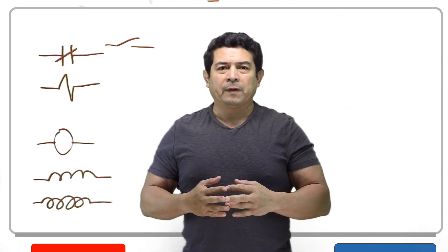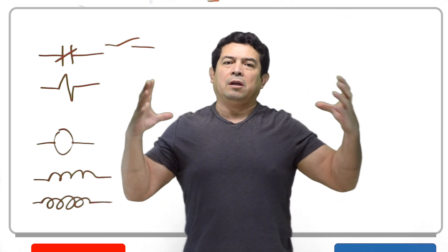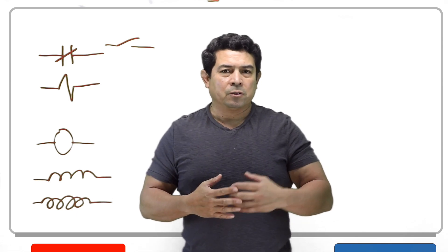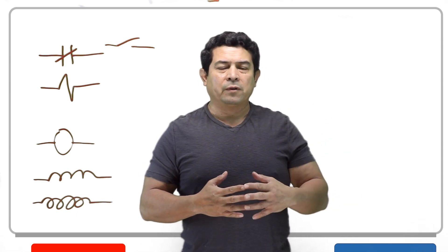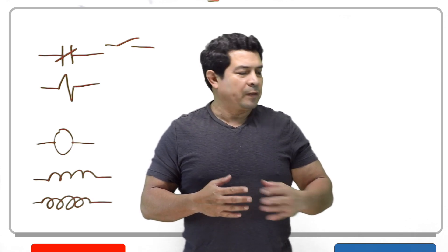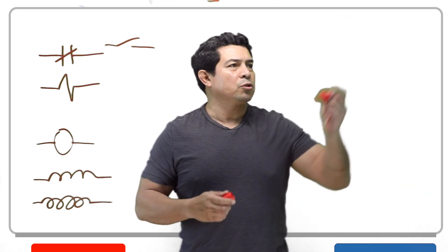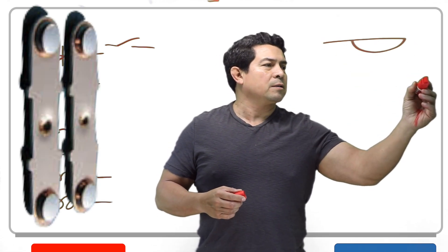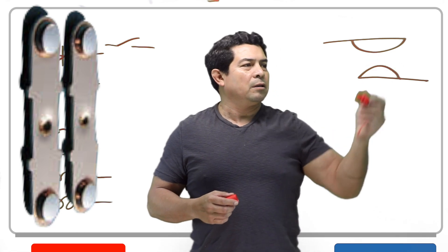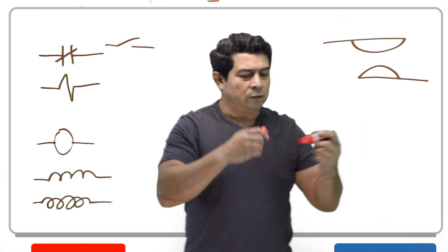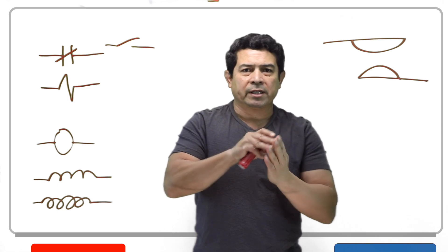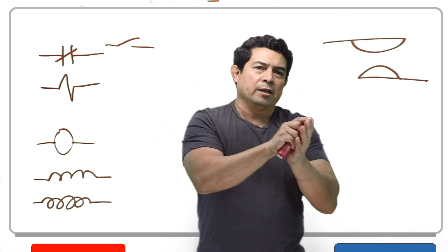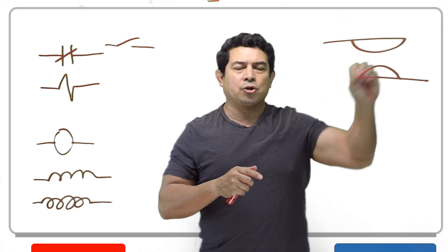Now you have small motors and you have great big motors. The contactor has to handle that amperage. So we need to make sure that you get the correct rating for the contacts. Now the contacts are supposed to more or less look like this. And when they close, they're actually going to rock into place and rock out. They don't just slam, but they're going to rock in and rock out to get a good connection.